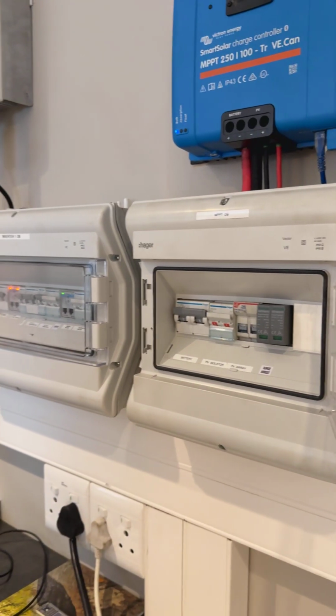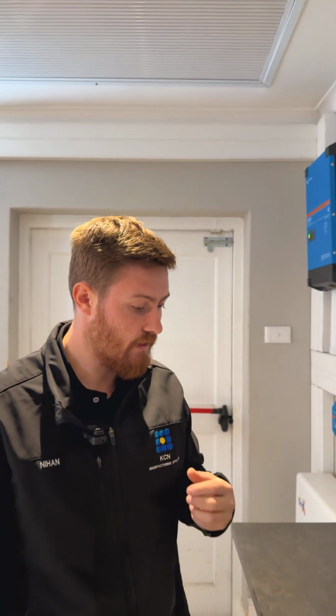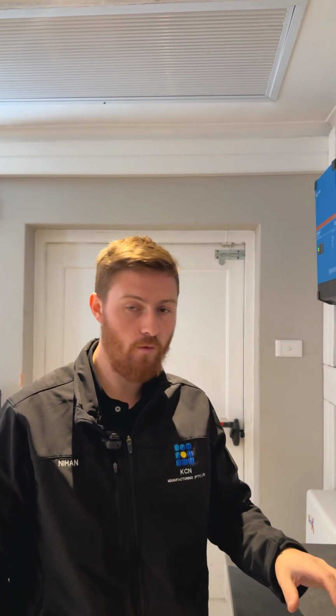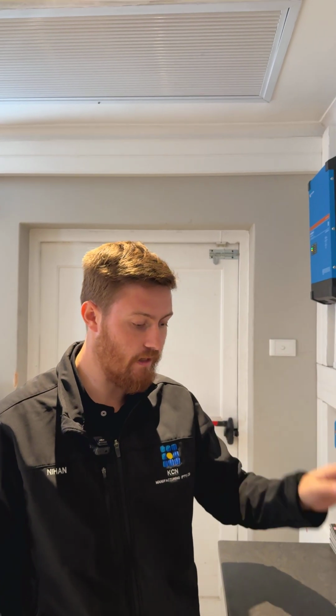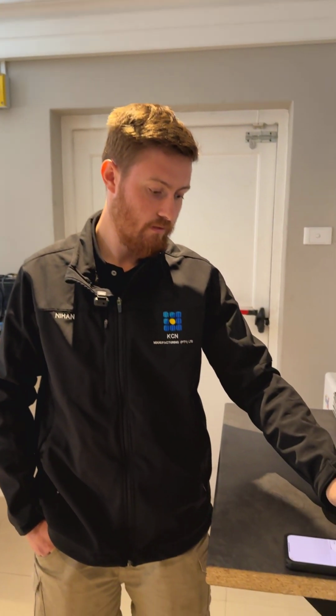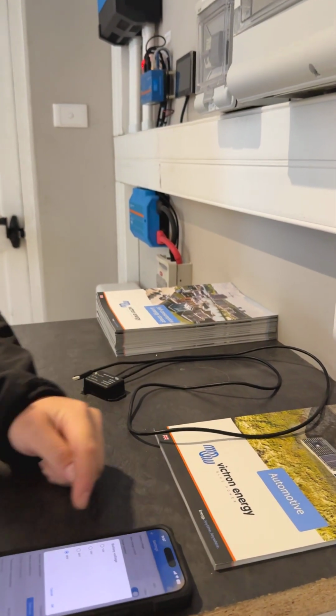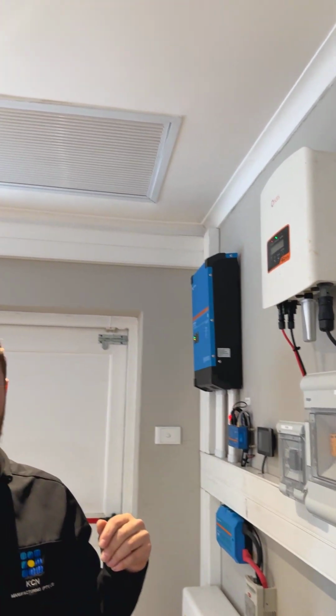What I found happened before in older models, before they added protection, is that once you update, it can automatically revert your battery voltage setting to a lower voltage, like standard 12 volt or 24 volt. If your battery side is already connected at 48 volts, this burns the MPPT out, and if it's an older model outside the 5-year warranty, you're left with a product that doesn't work.